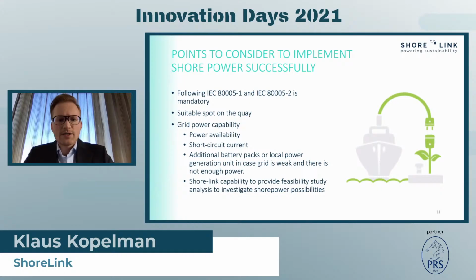The next important point is finding a suitable spot on the quay, whether stationary or mobile equipment is to be installed. The third important point is to have enough grid power to provide the energy to the ship. Also, the short circuit current the grid has to be able to resist, and to switch on and off the big and powerful transformer units. In case the grid is not strong enough at the port, additional battery packs or local power generation units can be used to generate the power.